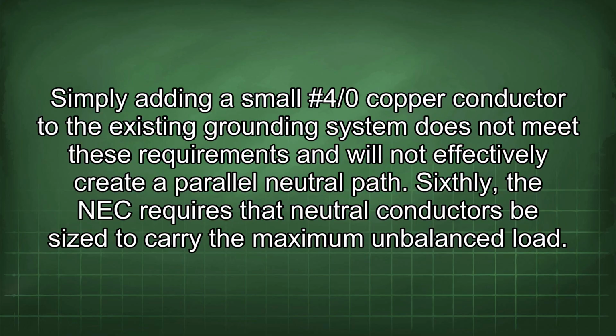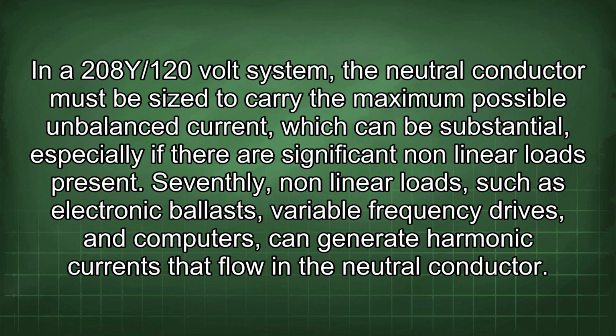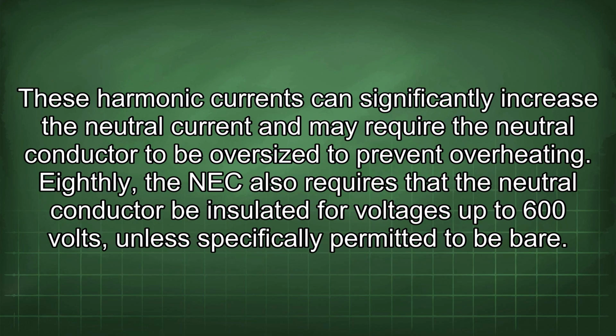Sixthly, the NEC requires that neutral conductors be sized to carry the maximum unbalanced load. In a 208Y/120 volt system, the neutral conductor must be sized to carry the maximum possible unbalanced current, which can be substantial, especially if there are significant nonlinear loads present. Seventhly, nonlinear loads such as electronic ballasts, variable frequency drives, and computers can generate harmonic currents that flow in the neutral conductor.